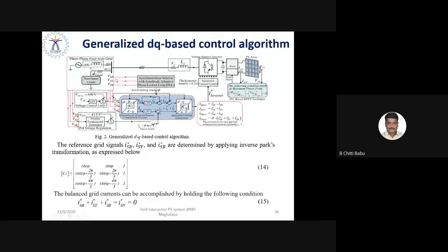So we sense the three-phase AC voltage as well as the three-phase AC current, and moreover, as you are implementing maximum power point tracking in the boost converter, we sense the PV current and the PV voltage, which are given to the incremental conductance based MPPT technique. So that will take care of the pulse width modulation, the PWM generation for the boost converter, so that you are able to extract the maximum possible power, right? As for the control loop, we apply cascaded control: the outer voltage control and the inner current control. The outer voltage control basically regulates the DC link voltage.